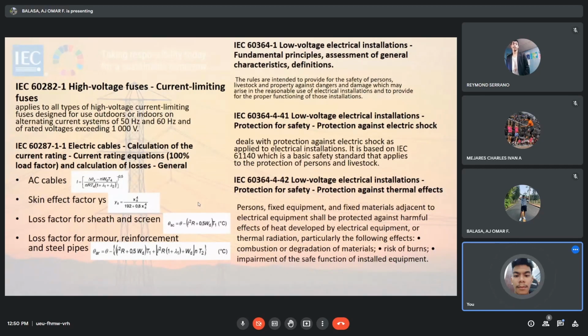It is recommended that special measures be taken to protect against the effects of arc faults in final circuits, in premises with sleeping accommodation, and in locations with risk of fire due to the nature of processed or stored materials. Example, BE2 locations: barns, woodworking shops, stores of combustible materials. In locations with combustible constructional materials, example, CA2 locations: wooden buildings. In fire propagating structures, example, CB2 locations. And in locations with endangering of irreplaceable goods.